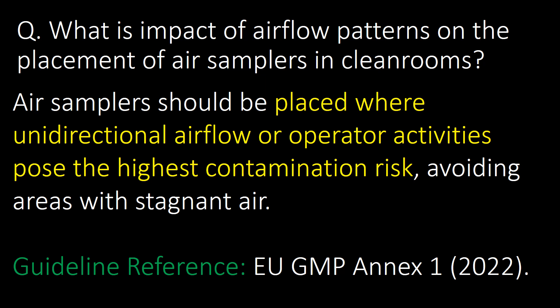What is the impact of air flow patterns on the placement of air samplers in clean rooms? Air samplers should be placed where unidirectional air flow or operator activities pose the highest contamination risk, avoiding areas with stagnant air. Guideline reference: GMP Annex 1.